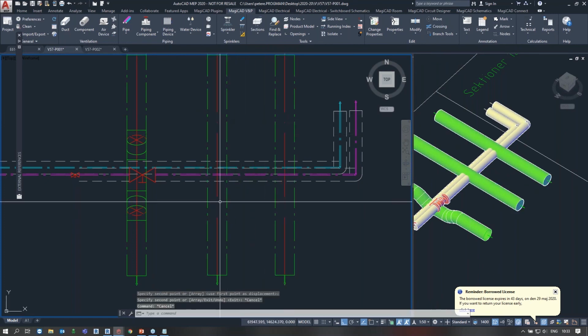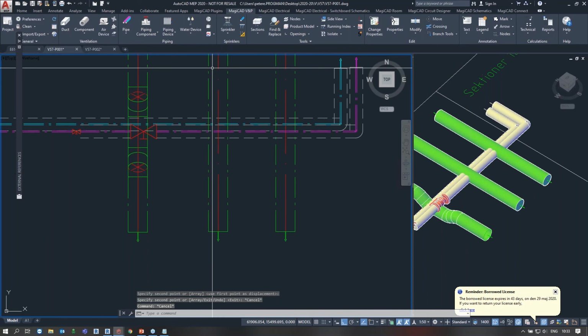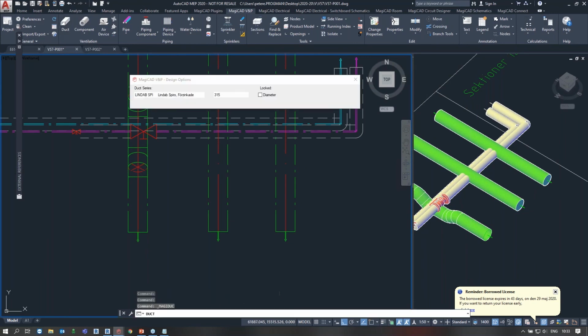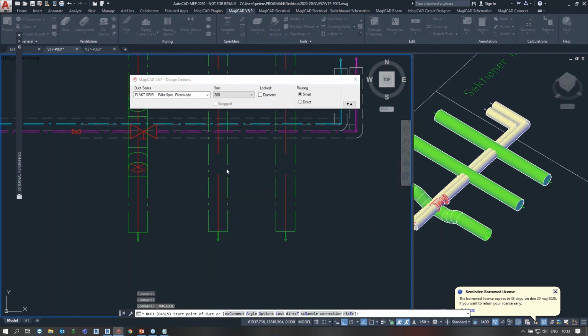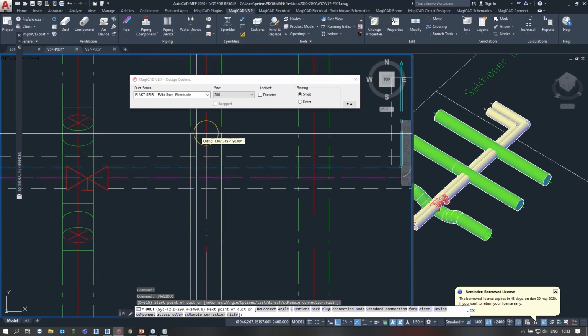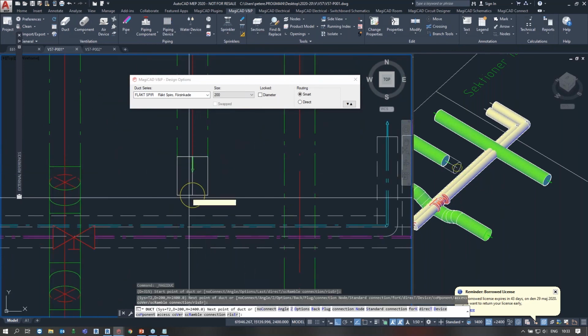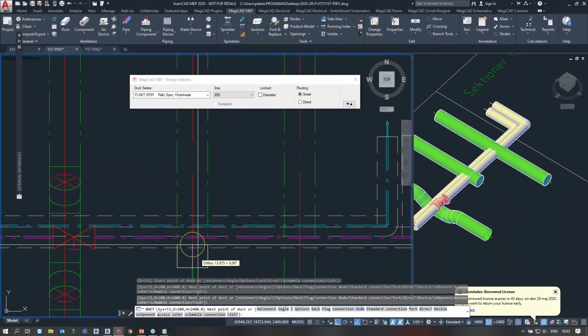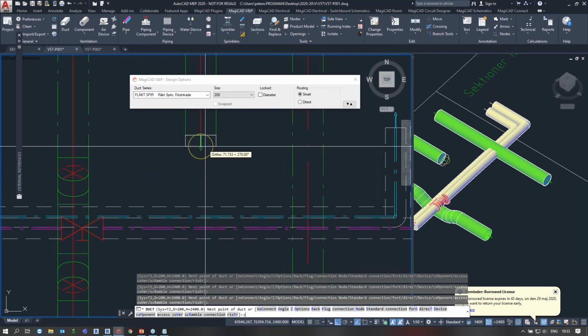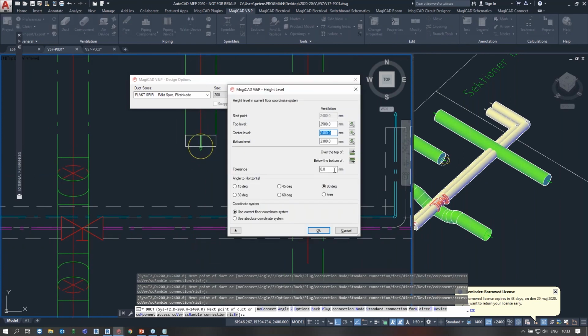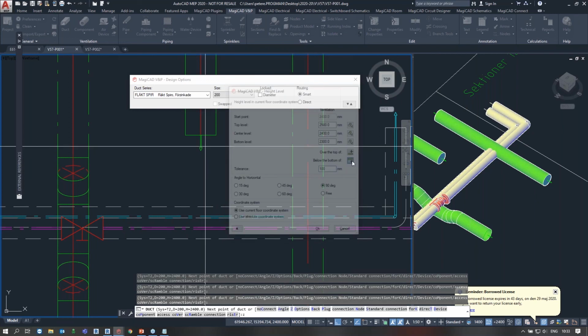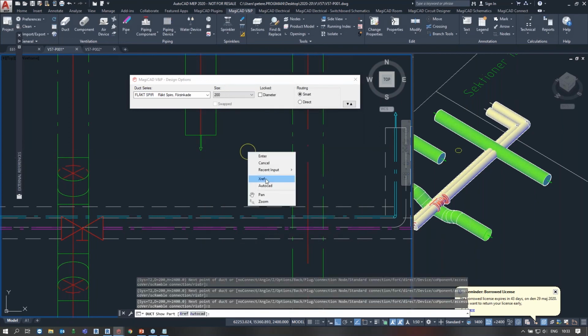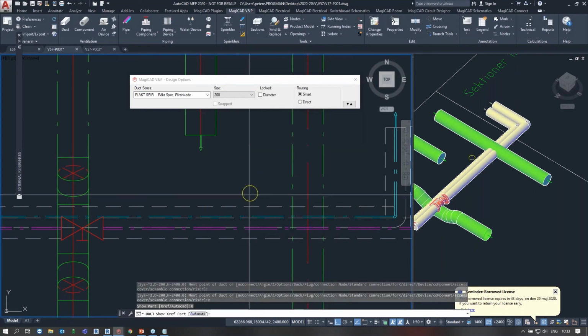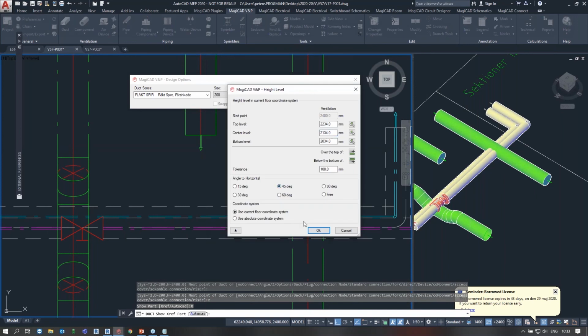If I notice this while drawing, I can avoid the collision. If I go here, I see I have a collision. If I go at the same height, maybe I need to go in the Z direction. Maybe I want some tolerance, 100 millimeters, read below the bottom, and read the height from the XREF. I say okay, I want to go under with 45 degree bends.